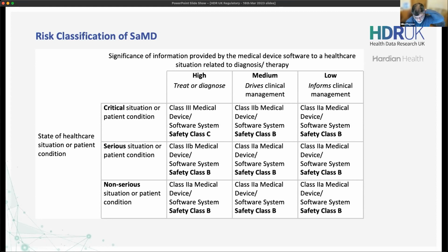We'll talk about risk analysis towards the end. The point being that a summative usability analysis says, if you found through your risk analysis that there are any particular risk mitigations, so things to prevent a person's condition becoming more seriously wrong or critically wrong, and for that risk control measure to be effective, so for it to work, there's a human factor involved, then you consider summative usability evaluation. You create a test with a representative cohort of intended users that says, we are going to train you to use the device.